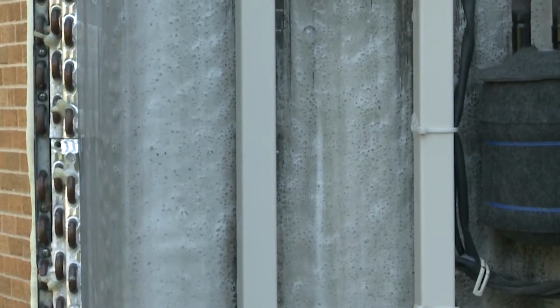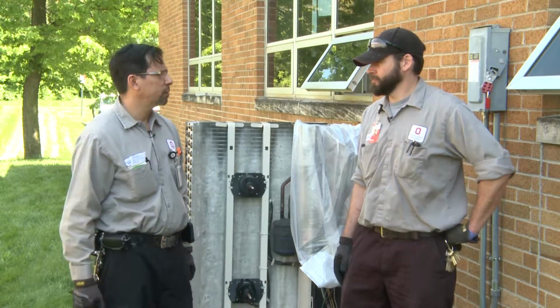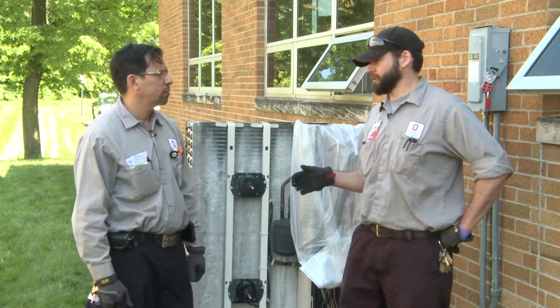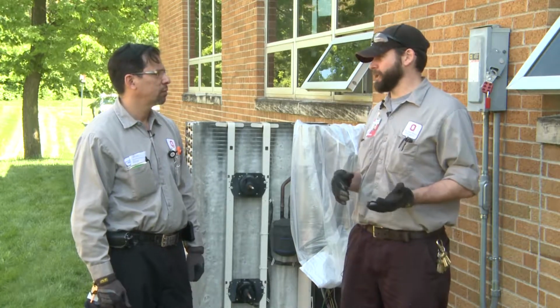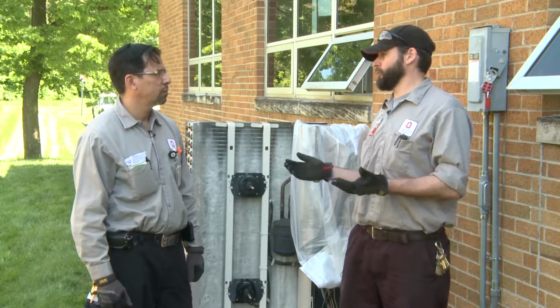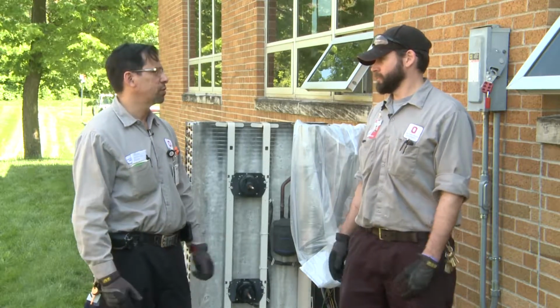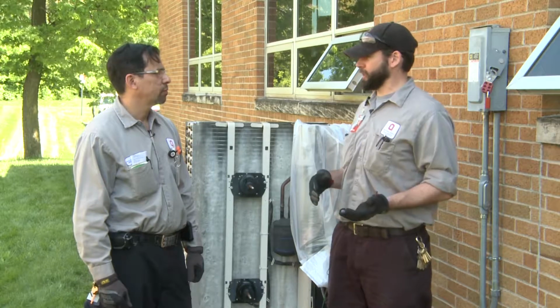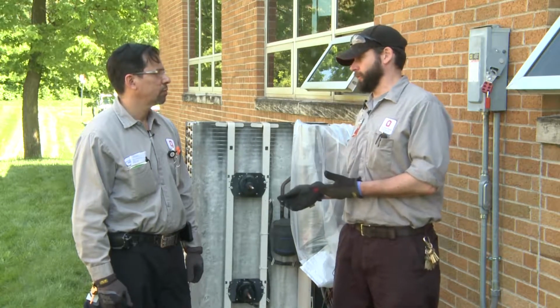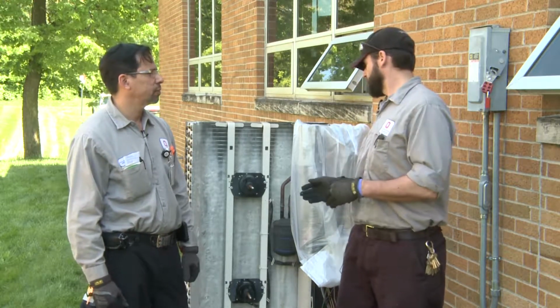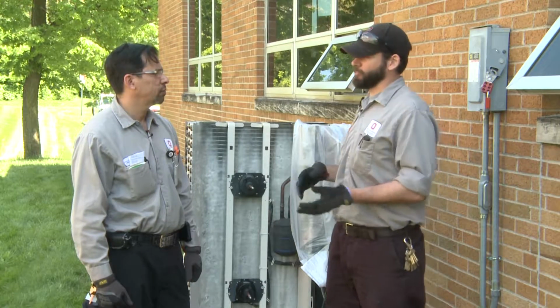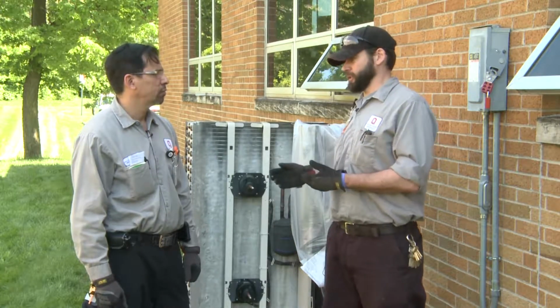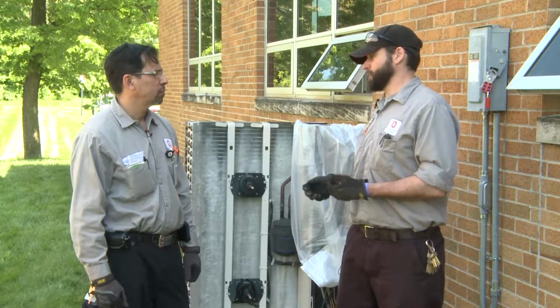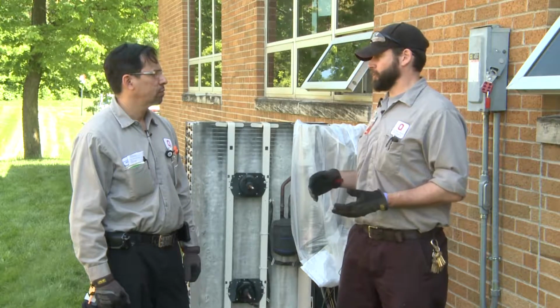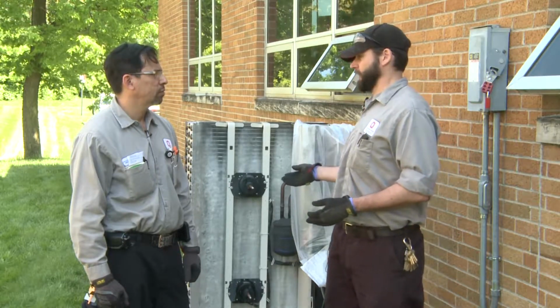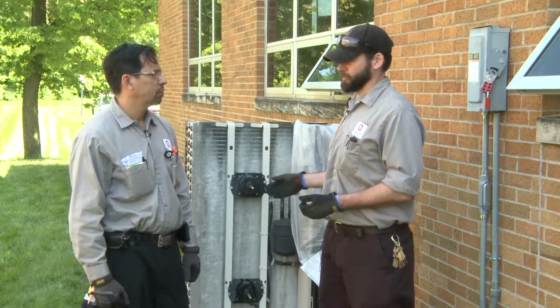So Mike, why are we actually cleaning this coil? Condensing coils need cleaning because they need to dissipate heat, and all coils are heat exchangers. So if you have a clogged heat exchanger, you're not going to exchange heat very well. Once we get this coil clean, we'll have a more efficient system. An inefficient system could lead to high head pressure, which could lead to wearing out the compressor early, and excessive fan use, wearing out fans and fan motors early.